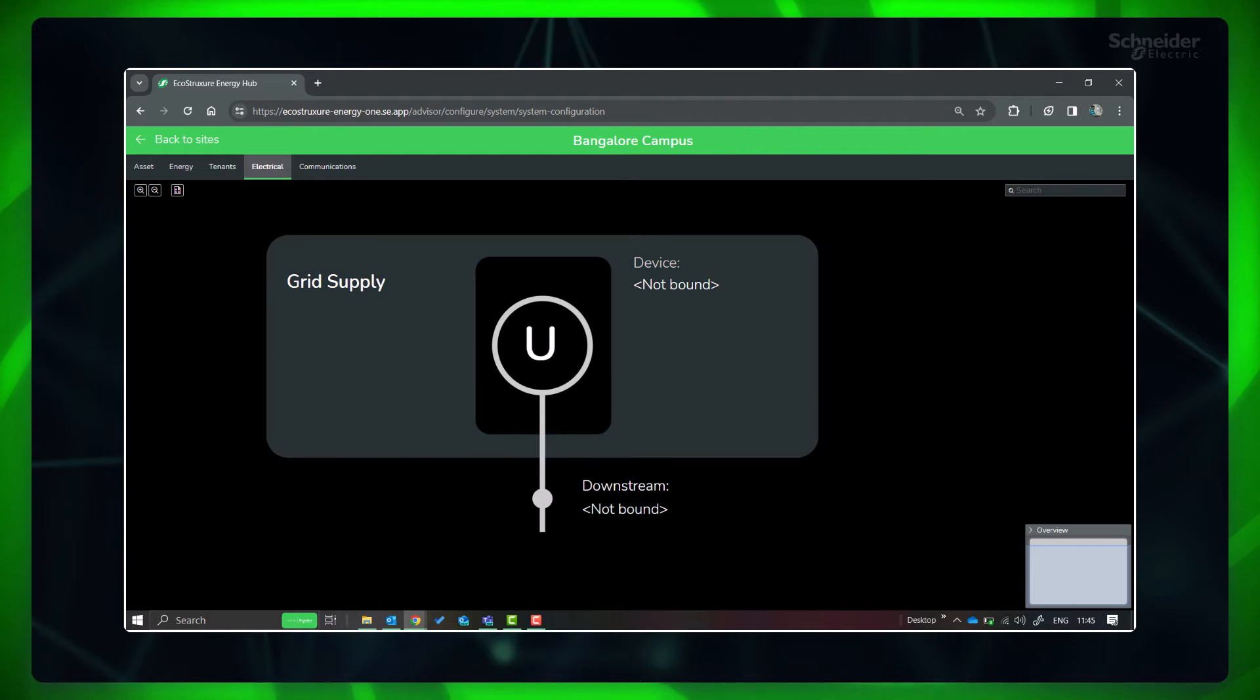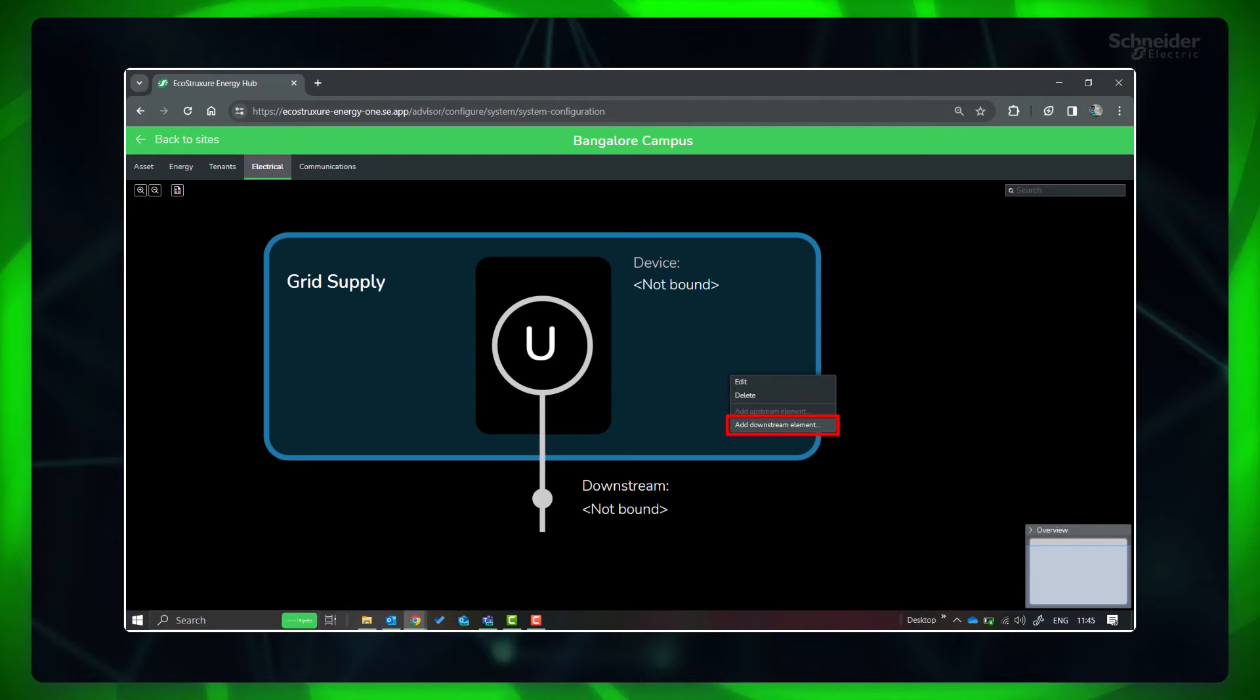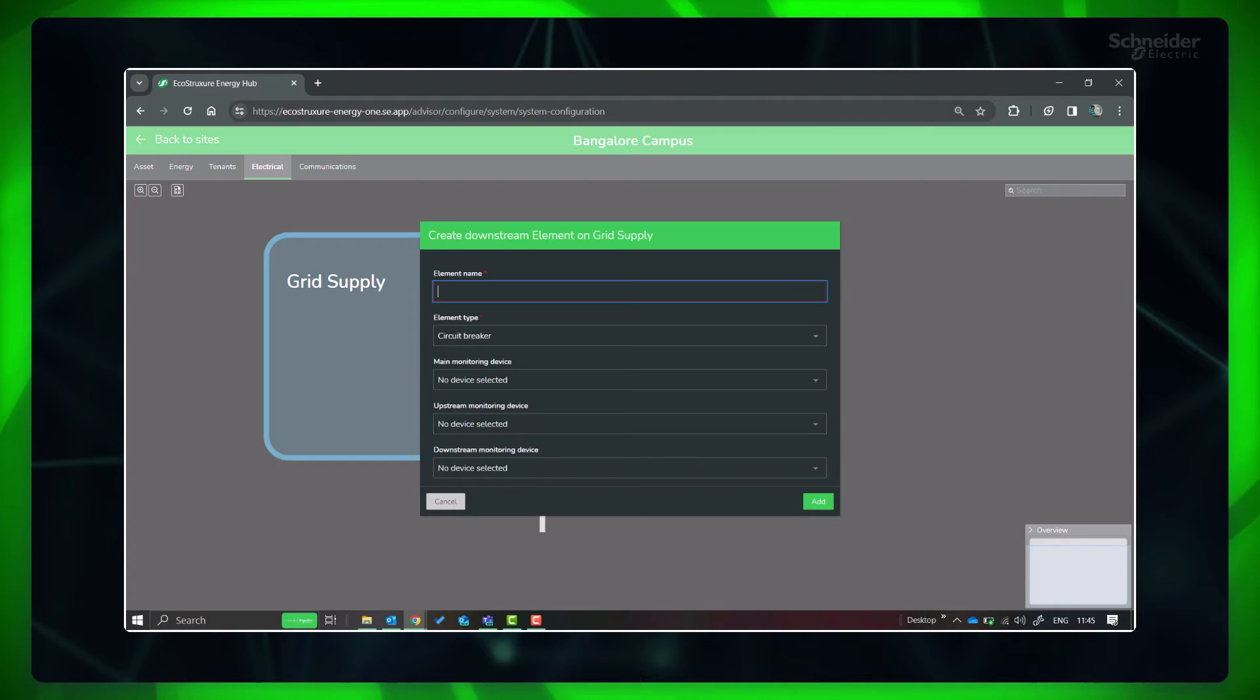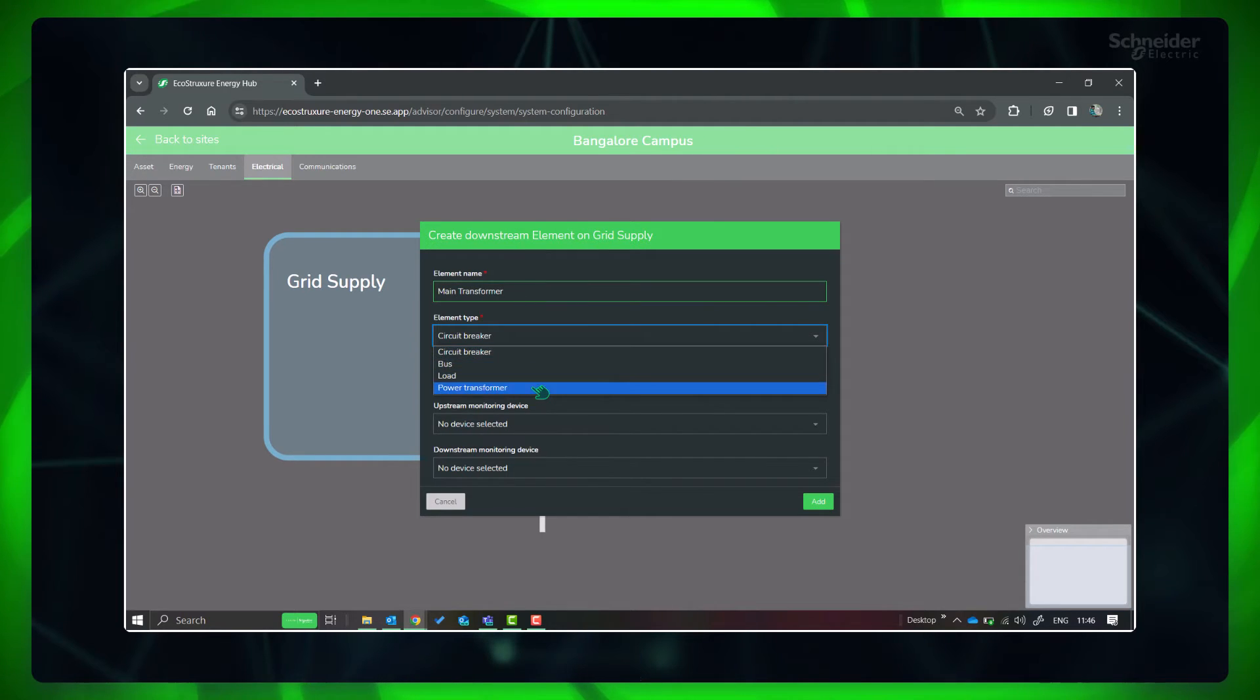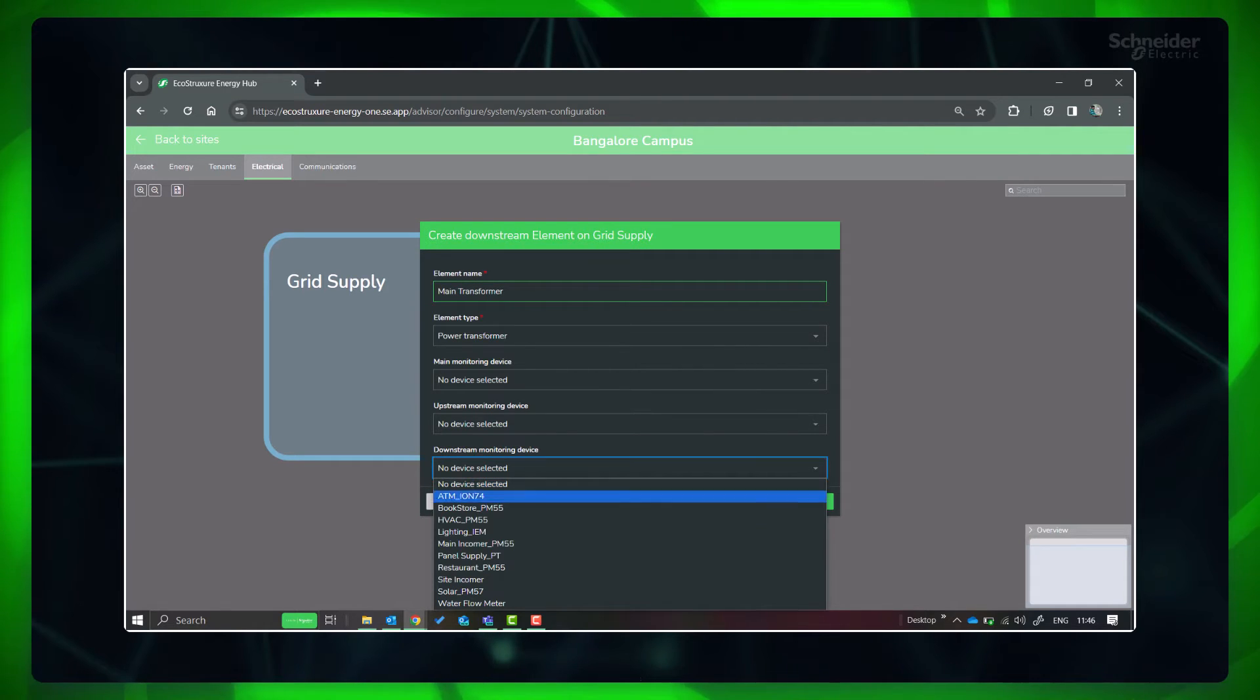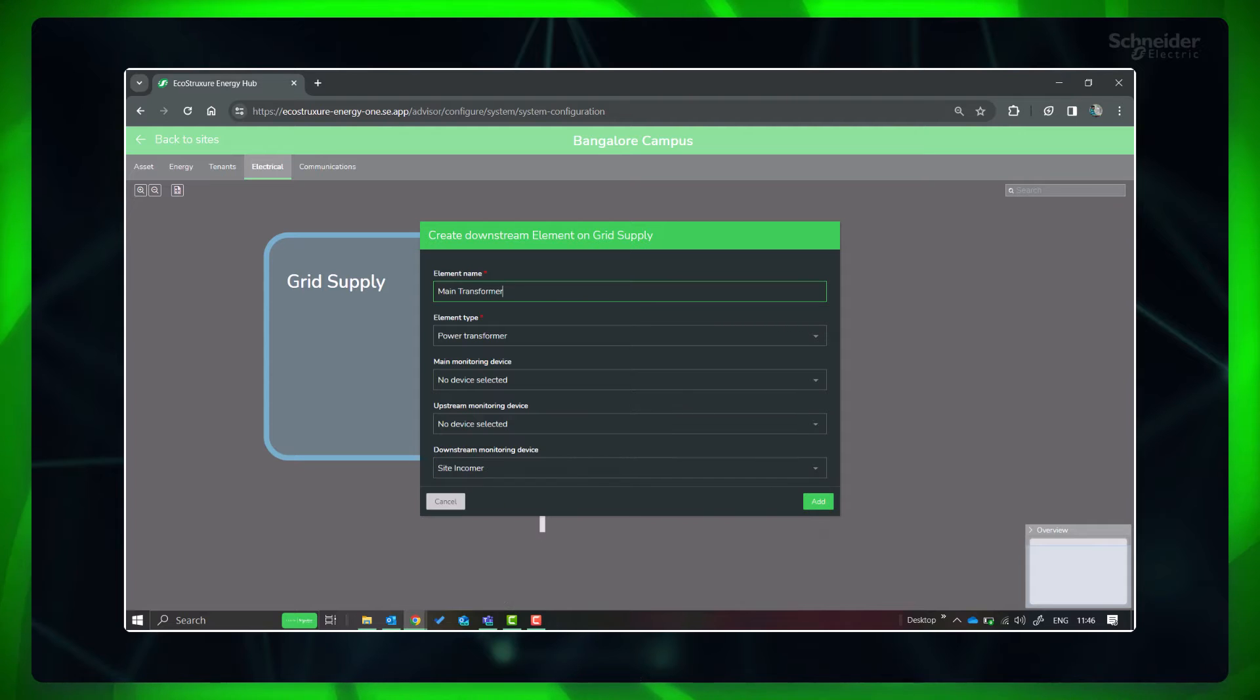Next, to add a connecting element, select this existing element and right click and select Add Downstream Element. Provide the name and select element type as power transformer. In this site, we have the site incomer meter connected at the transformer secondary. Click the downstream monitoring device and select site incomer from the dropdown options.